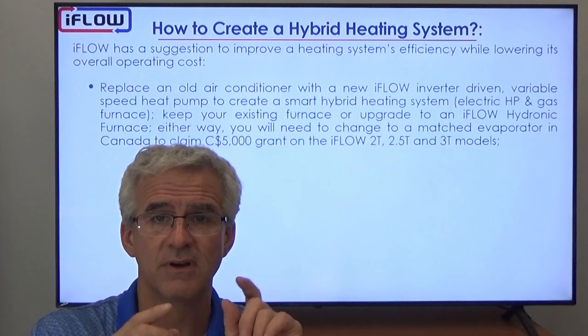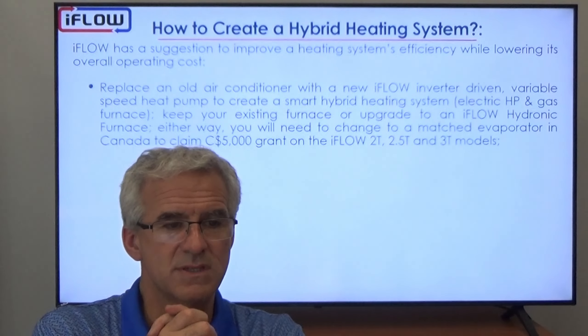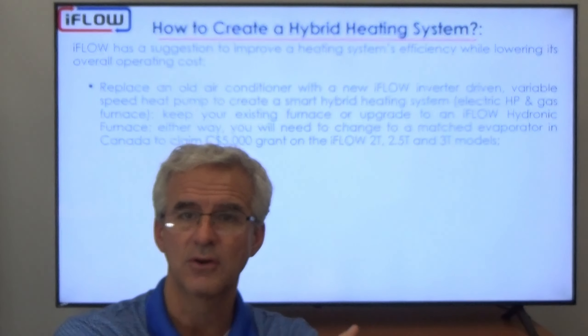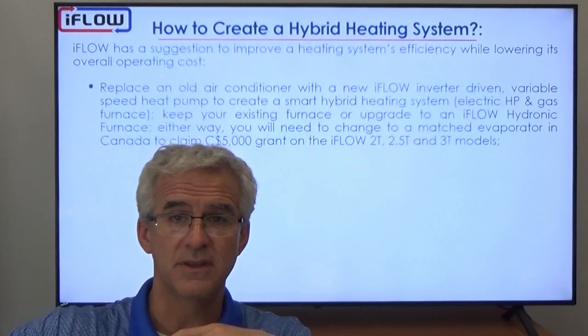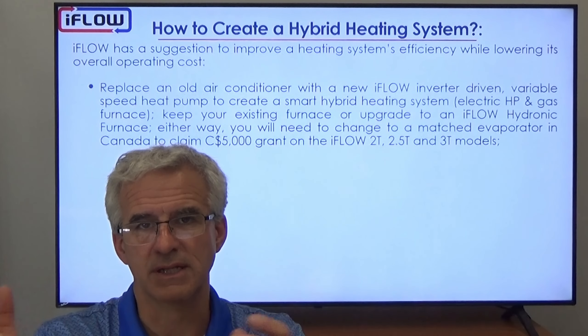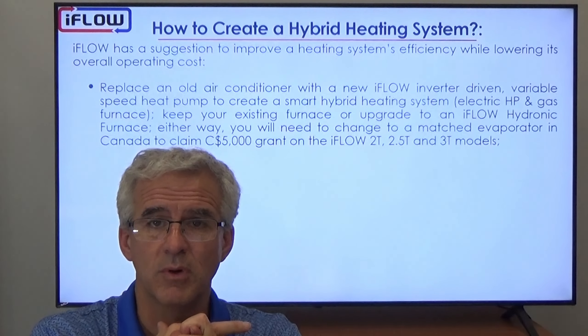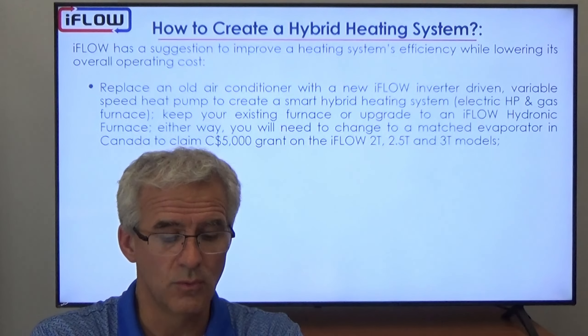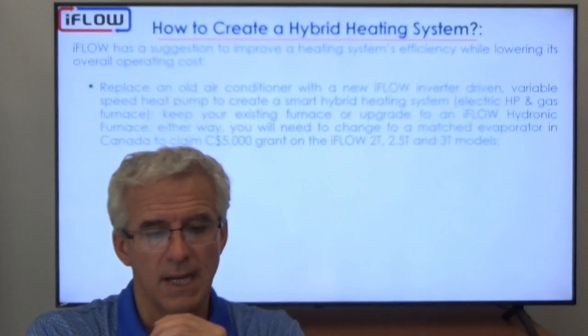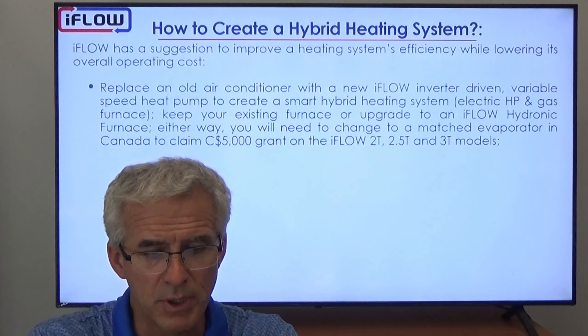A heat pump is just an air conditioner unit that can run backwards through a reversing valve — it changes the refrigerant flow so that instead of taking heat out of your house to make it cooler, it puts heat into the house and takes it from the outside. The heat pump will still give you air conditioning all summer the same way, but it will also provide heating in the winter. We replace that old air conditioner and put in a new iFLOW inverter-driven variable-speed heat pump.